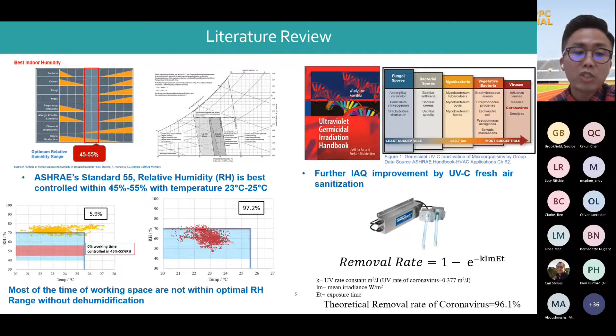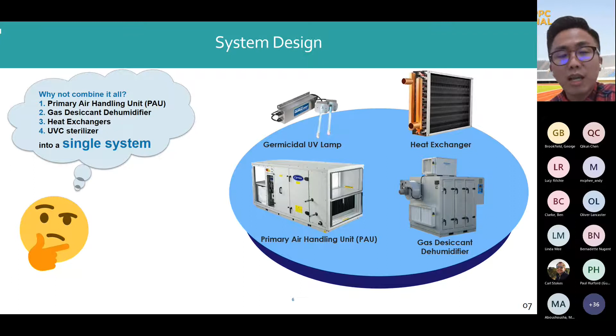To achieve space saving, I've coordinated with the contractors and manufacturers to find a way to integrate the necessary components for the gas dehumidification into the primary air handling unit, including the desiccant wheel, the heat exchanger for the hot water, and the germicidal UV lamp, so that we don't need extra space to install a standalone desiccant dehumidifier. The functions of fresh air dehumidification and fresh air sterilization are combined together, so we call this product the integrated PAU, because there is a desiccant wheel inside the primary air handling unit.